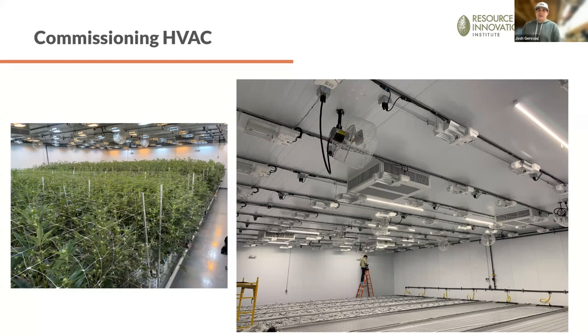So the things you'll run into really happen during those lights-off growth stages. Right as the lights kick off, you're going to have a humidity spike. I don't care how good you get at dimming your lights or adjusting controls, you're always going to have a humidity spike you need to deal with. And if you don't have supplemental dehumidification, or a gas reheat or electric reheat setup on your HVAC equipment, those are the areas where you're going to run into problems.